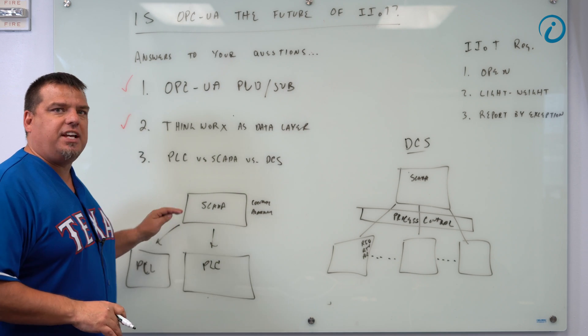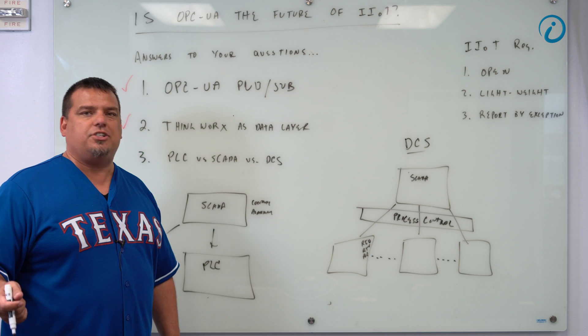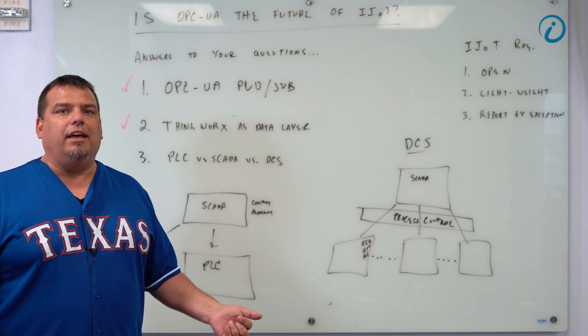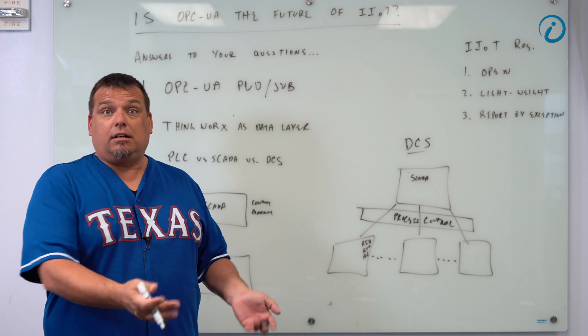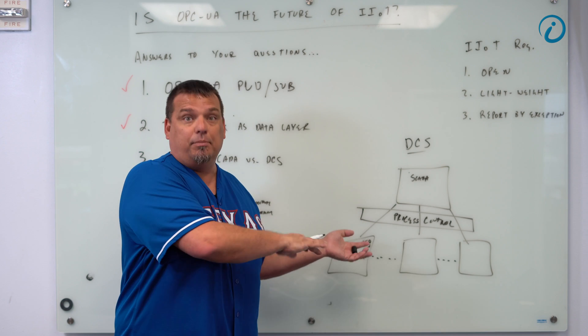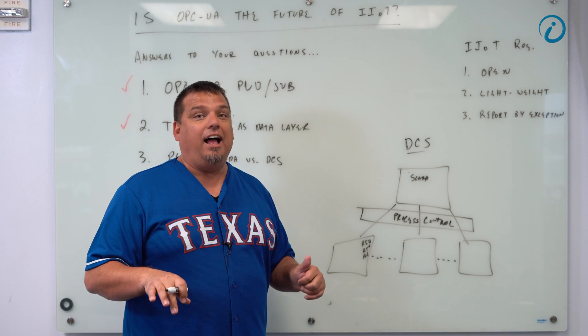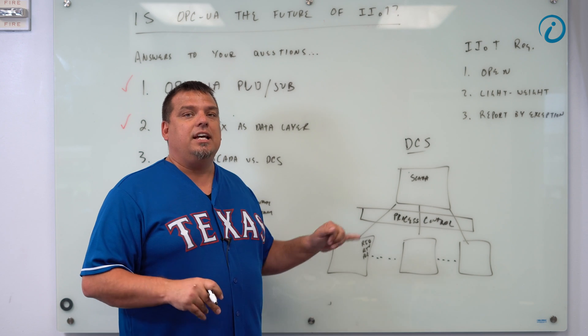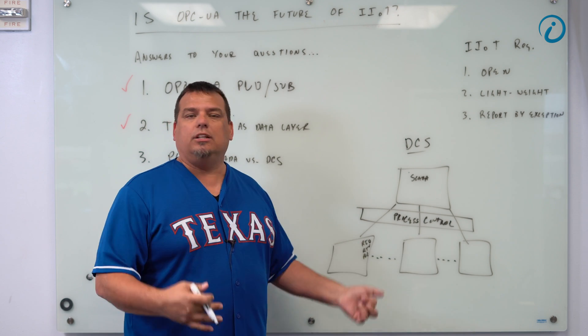With PLCs and SCADA system, think of them as blank slates. When I buy an Allen Bradley ControlLogix, it doesn't have a program on it. I can take a program I've already written and put it on there, or I can just write a new one from scratch, which is the way it normally works. A distributed control system can come completely blank. But in this day and age, normally it does not. Normally the DCS comes with the program to run your process already loaded onto it.